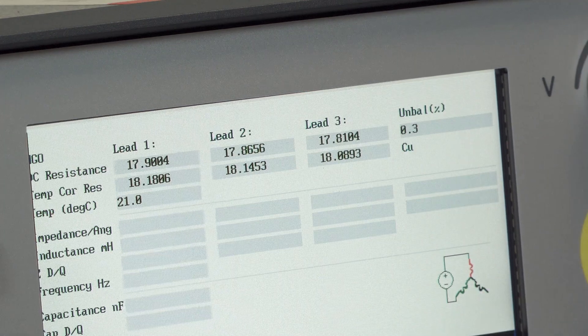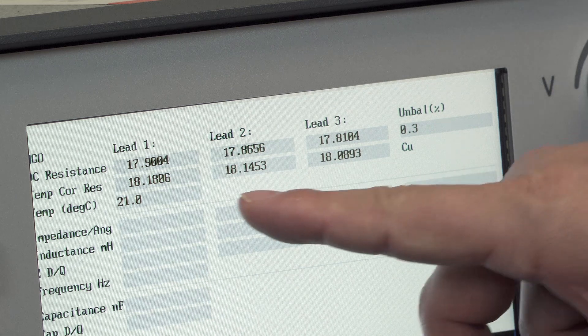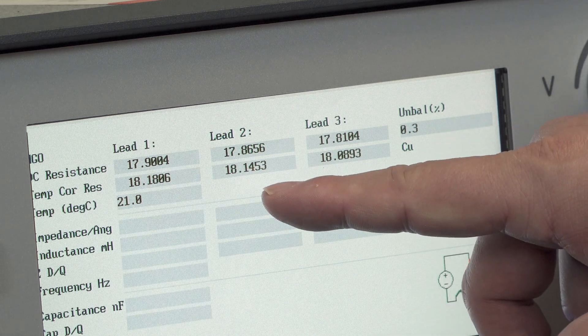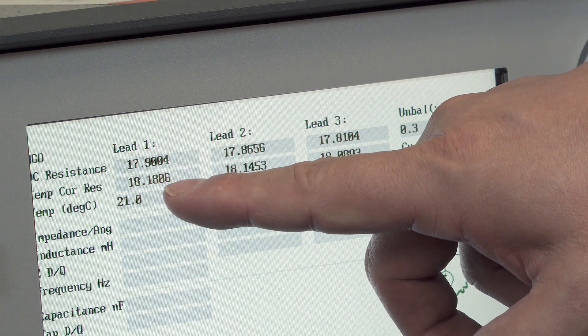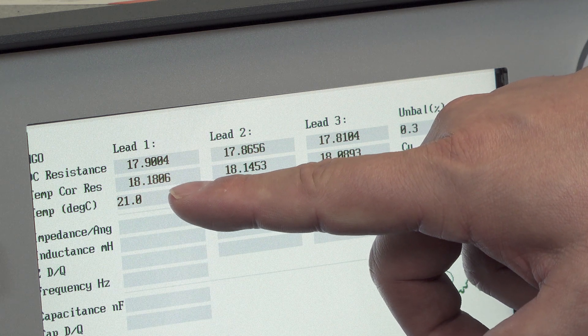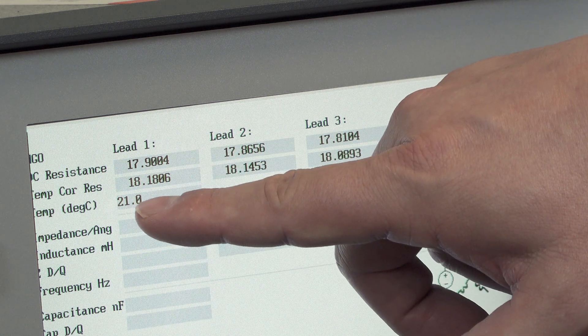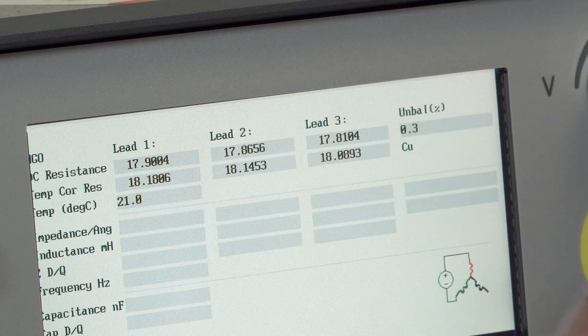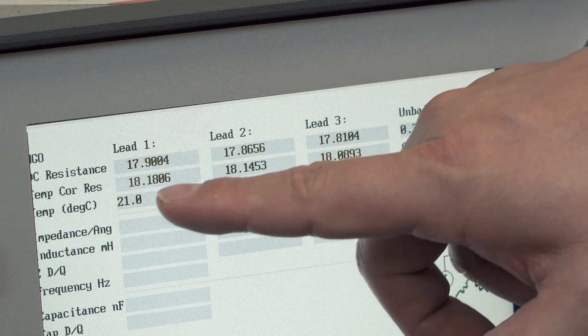Okay, so from the results we see the results from each line to line resistance measurement. The temperature corrected value is given underneath the measured value. The temperature of the winding is also indicated here in the first column.